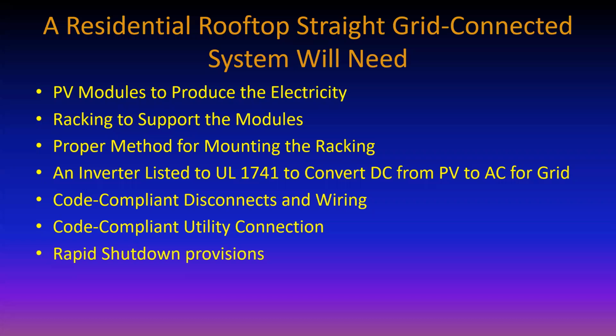Some people say, why does it work that way? The reason is that the photovoltaic inverters that are grid connected act as current sources. A lot of people don't distinguish between voltage and current, but it's very important in this case, because as a current source, it will deliver current to the grid only if there is grid voltage, because the grid voltage acts as a synchronizing signal. If that synchronizing 60 hertz grid signal is there, then the inverters assume the grid is in good condition and they deliver their electricity. But if the frequency of the grid varies too much, or if the voltage goes too high or too low coming in from the grid, the inverter interprets this as a problem with the grid and it shuts down. That's what UL 1741 is all about. It verifies that the inverter has been tested to that and it meets the IEEE 1547 specifications. All right.